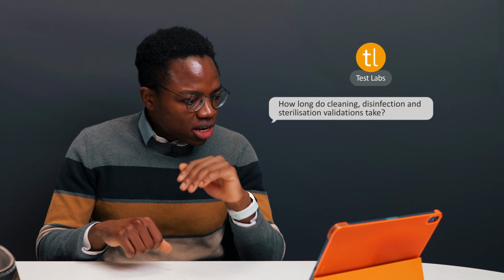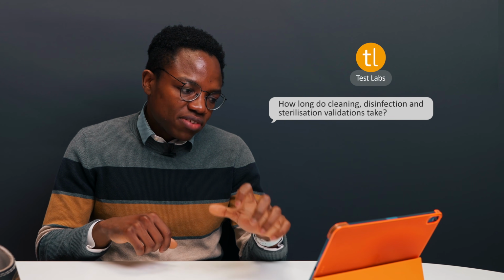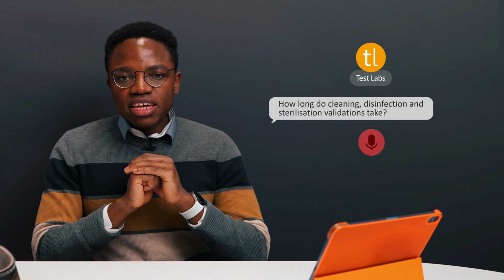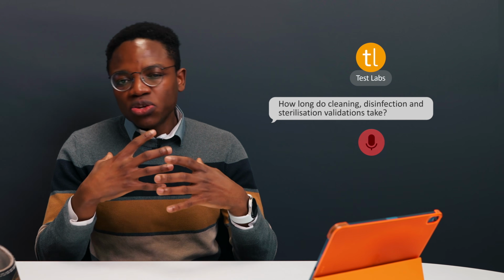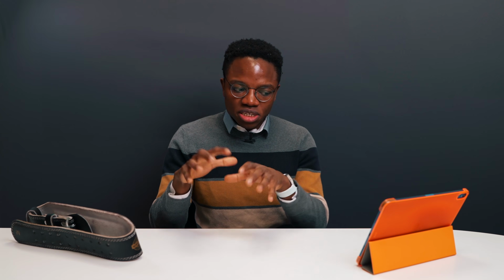Now, the next question is more laboratory based, and this is, how long do cleaning, disinfection, and sterilization validation take? So the inception of this is that basically I'll use test labs as an example. So you might contact us and we basically have a mini consultancy session where we would help you and tell you exactly what you need and what you don't need and exactly what we expect you guys to provide us as medical device manufacturers for the best possible evidence to be generated.